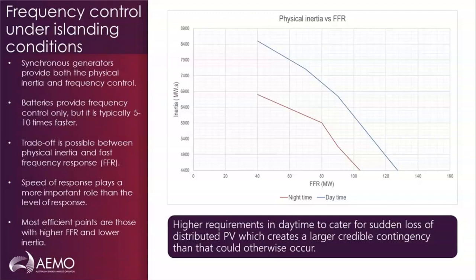This graph shows the operating envelopes that we determined from the simulation studies in terms of how many megawatts of FFR is needed in addition to how many megawatt seconds of physical inertia. As you can see, there are sets of operating envelopes, meaning that there are multiple points on these two curves that we can pick and operate the power system accordingly. The question that comes up is efficiency, by which I mean that, as we can see here, by having a small increment in how much FFR we have in the power system, we can save several hundred, if not thousands, of megawatt seconds of physical inertia.